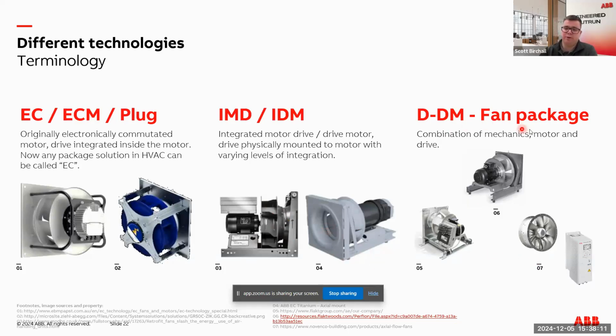Then you've got the discrete drive and motor package, where the fan is generally installed with the motor and the drive is separate, controlling the fan, which again has its pros and cons. There's a lot more flexibility in this option than the other two, and replacing and servicing parts is much easier with this option. But you've got to consider the pros and cons, which we're going to move on to in the next few slides.